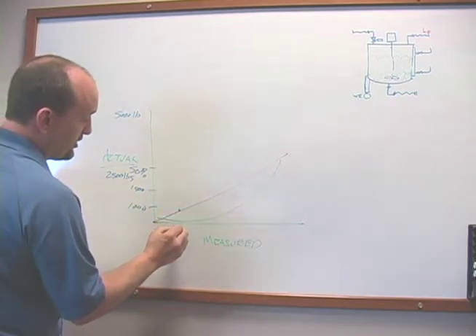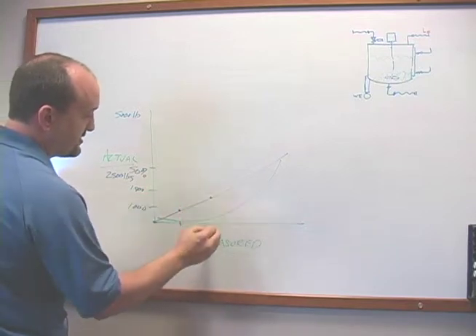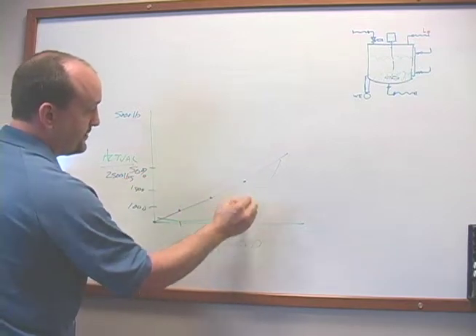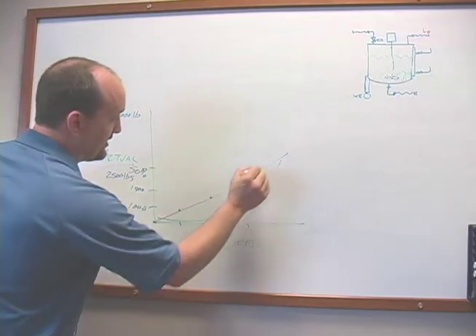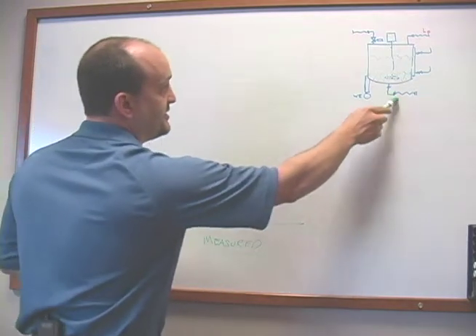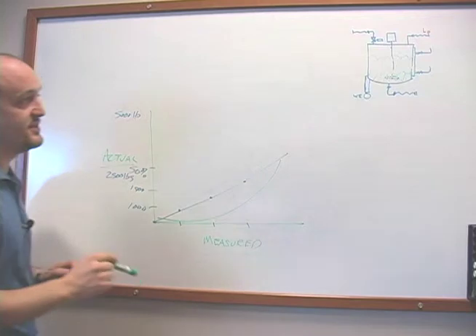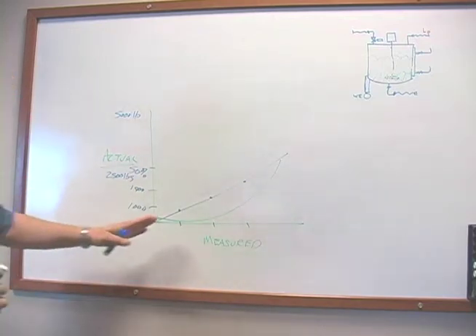And then look, when you add that known weight, look at what your load cell system says. This is after you've zeroed. Most of the time, this is going to be a straight line. The reasons it may not be a straight line is if you have some loads, some resistance on the tank that are causing different resistance. And that's what we want to know.